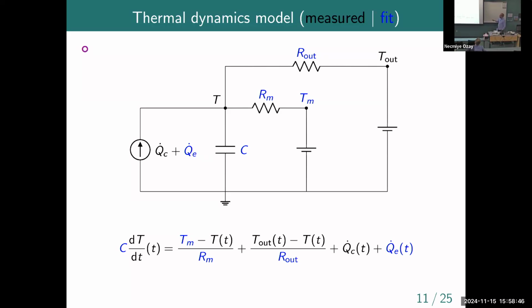But you can easily change this voltage source here to a capacitor as well and do some model-based estimation to figure out what that C should be. It's a challenge because the mass temperature is typically not measured. We have wall thermostats that measure air temperatures, but we don't typically measure the floor temperatures.